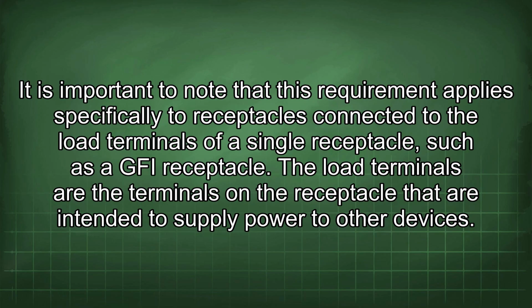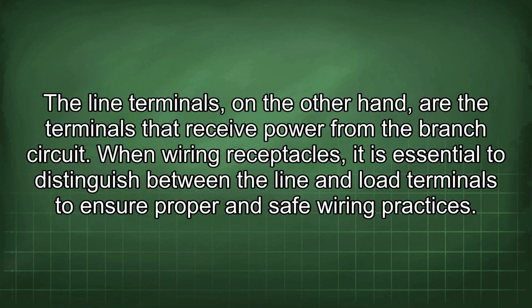It is important to note that this requirement applies specifically to receptacles connected to the load terminals of a single receptacle, such as a GFI receptacle. The load terminals are the terminals on the receptacle that are intended to supply power to other devices. The line terminals, on the other hand, are the terminals that receive power from the branch circuit. When wiring receptacles, it is essential to distinguish between the line and load terminals to ensure proper and safe wiring practices.